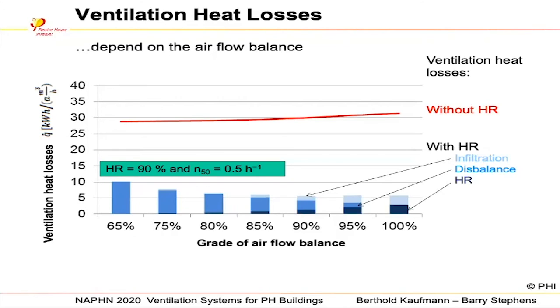And on the next slide, you see what about the energy. If you do 100% balance, you have the blue bar on the right-hand side. The blue bar is the remaining heat loss after heat recovery, so we do not have 100% heat recovery. Therefore, we have some remaining heat losses, as you see on the left axis. And the light blue is the infiltration heat losses.